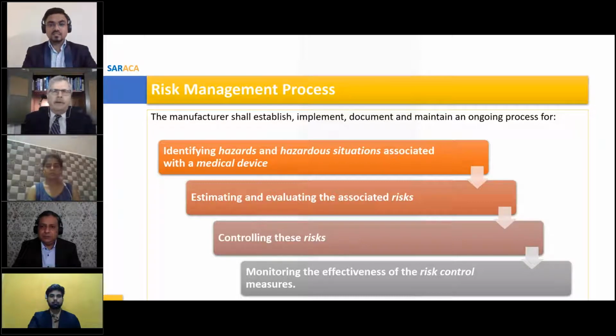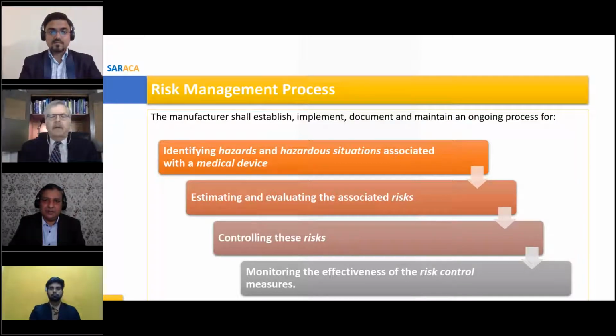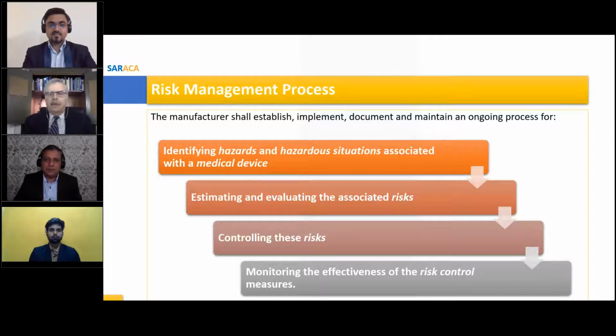I'd like to expand on that a little bit because I fully agree with you. Some of the notified bodies, as well as FDA, have come through the facilities I've been associated with. And even though we did effectiveness checks and we did document those, we did not go back as part of the internal audit process and look at those and document those as part of the internal audit. And the notified bodies want that done. They want that included in the internal audit, at least the notified bodies I've been associated with.